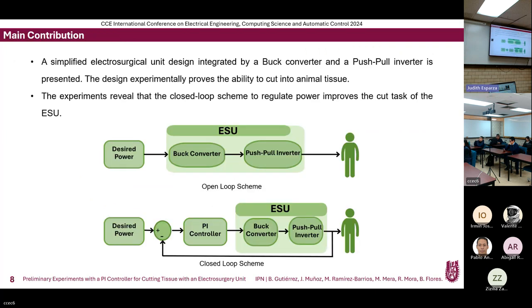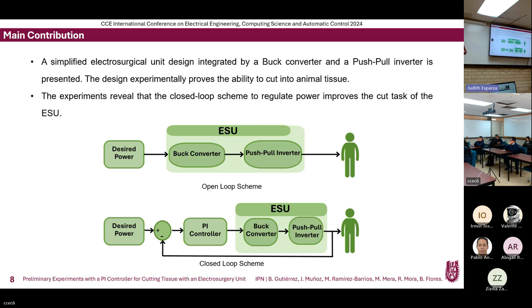Our main contribution focuses on closing the loop in order to regulate power and compensate for changes in impedance. We propose a simplified electrosurgical unit design composed of a buck converter and a push-pull inverter which is able to cut animal tissue, and our experiments reveal that the closed-loop scheme to regulate power improves the cut task of our ESU.